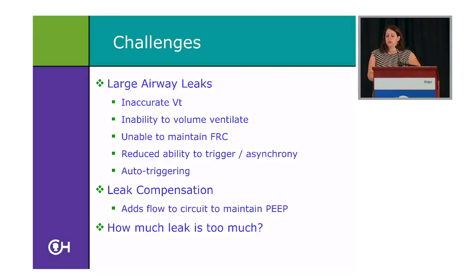So in addition to when you have your proximal flow sensor in line and you have this large leak, you're not getting accurate tidal volumes. You're getting the inability to really volume ventilate. You can't really maintain FRC. You're losing your PEEP as well as your volumes. You're reducing the ability to trigger. So your patient can't trigger even just with the airway sensor that close. So then you have your asynchrony again that we tried to get rid of by putting the flow sensor in line.